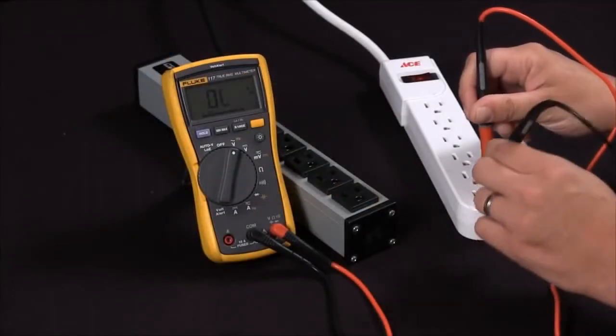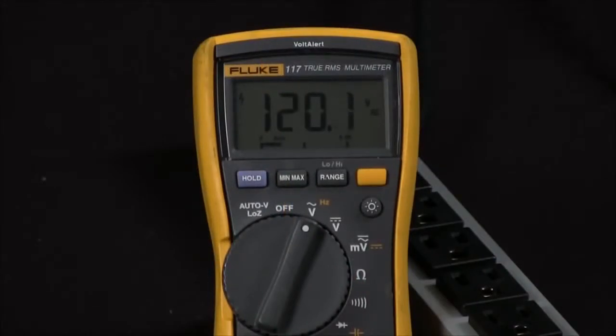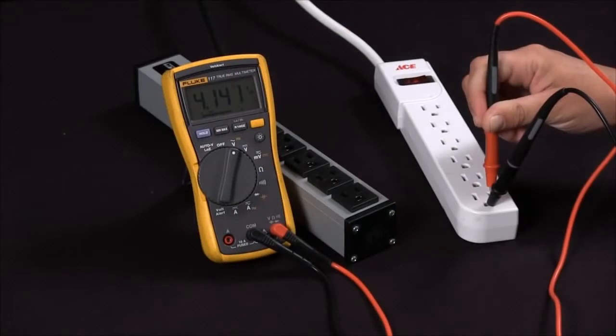Now if I go ahead and move that ground over to the neutral side I'm getting 120 volts. If I go back to my ground to hot I'm at 4 volts.